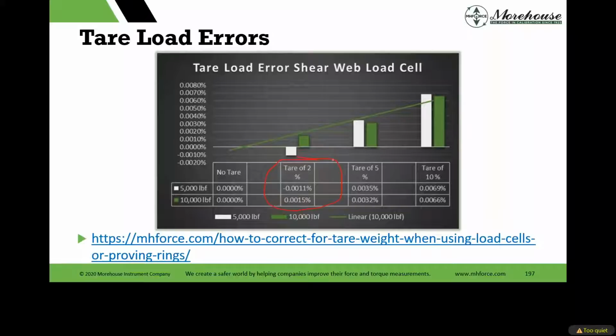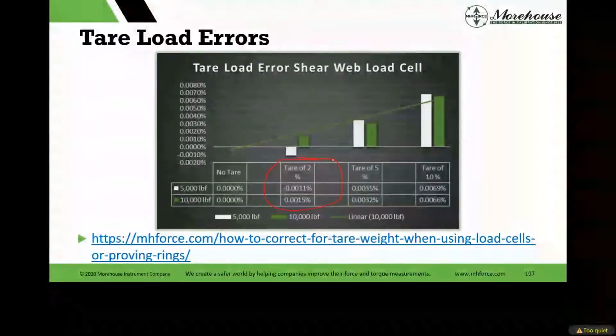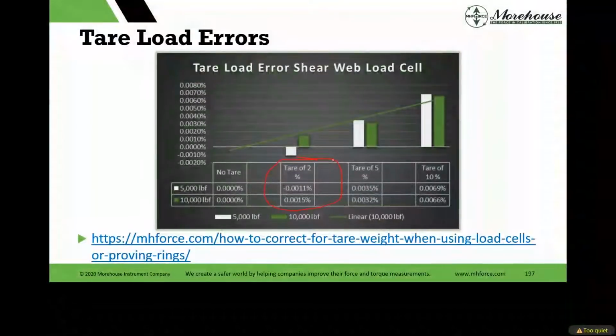And when I see numbers going high and low, and I consistently see a mash of numbers, I don't think there's much impact between Tare and no Tare as far as this. This is well within the uncertainty of the machine. Now, typically, I did say if you caught it earlier, most load cells in good machines will get repeatability characteristics of about 7 to 10 parts per million. So regardless, the number is really low.